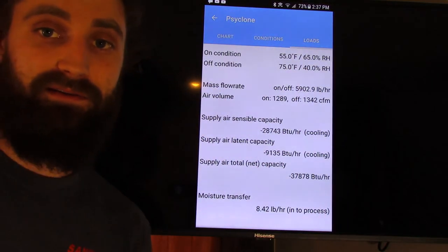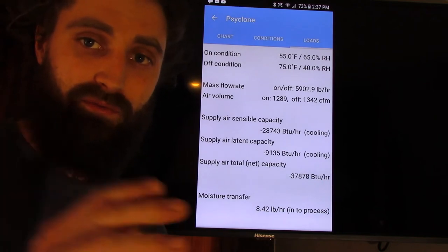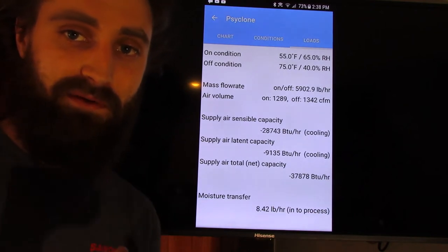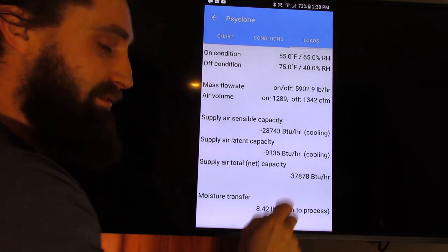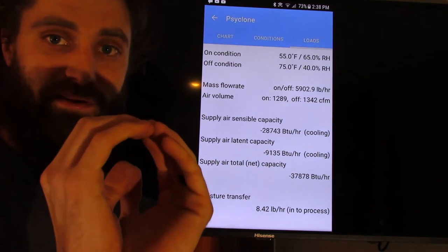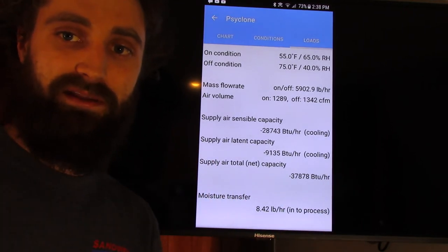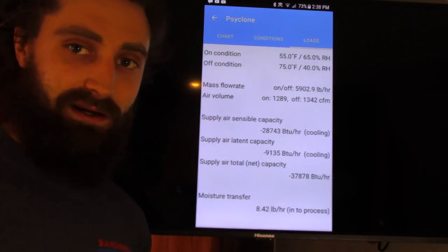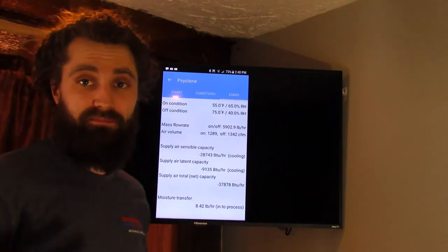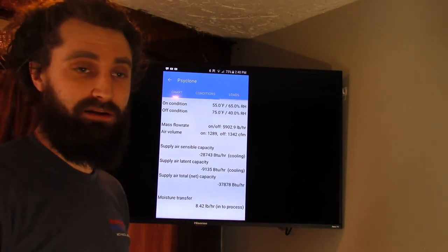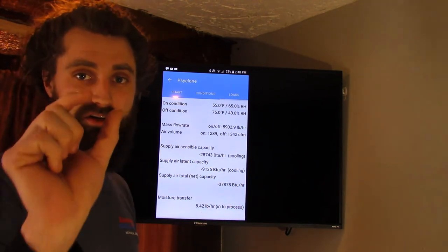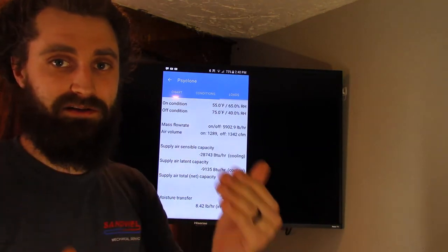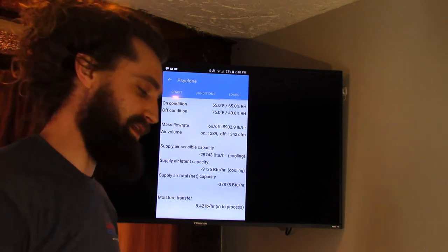So right there, that's just a difference of whether you go out in the morning or in the afternoon, or whether you go out on a Tuesday when it's 93 or a Wednesday when it's 80 degrees, okay? That unit is right there. The difference in a day. So 38,000 BTU is what that thing's doing. That's more than I can ask for. So essentially, you can tell that system's working good just with 5% humidity difference between one day and the next, or the morning and the afternoon, whenever you're testing these systems out.